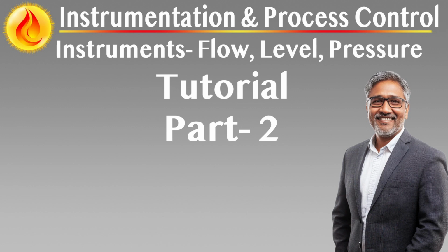Permanent accessibility. The instrument is within 1.7 meter vertically and 0.5 meters horizontally from a safe permanent walkway, grade, or platform with no obstructions. This is the target condition for all instruments requiring routine calibration, frequent manual checks, or test intervals under 2 years, e.g., IPF devices, flow transmitters, level alarms. Limited accessibility. Instruments located between 1.7 meters and 4.0 meters high, or up to 1.0 meters offset, accessible only by ladder or mobile platform. This is permissible for indicators or transmitters not requiring routine intervention, provided they are visible or maintainable from below using safe, approved methods.